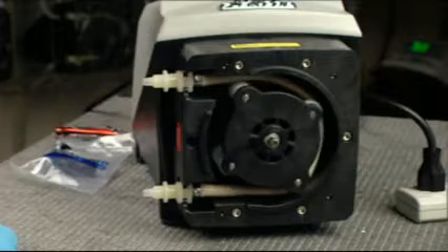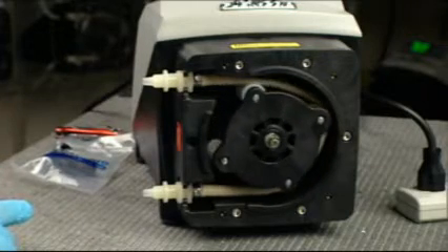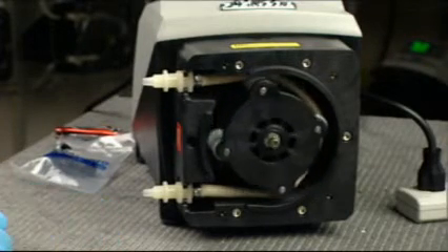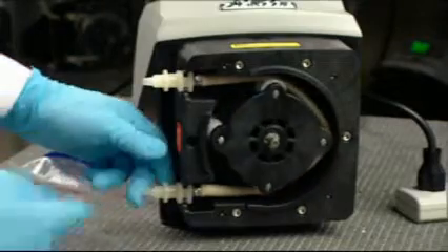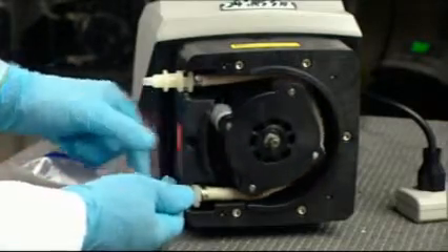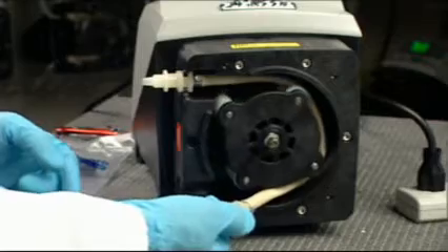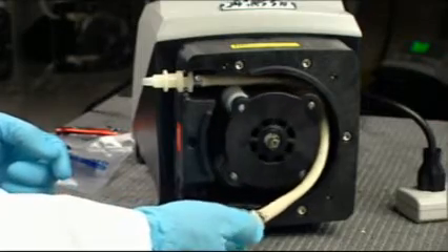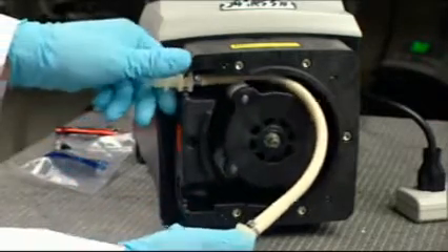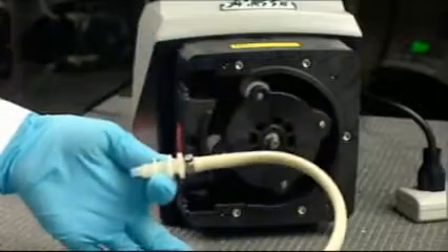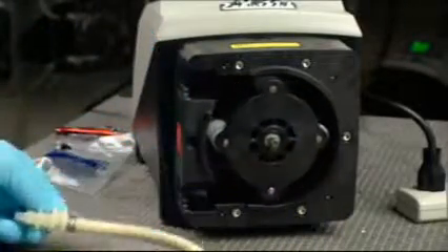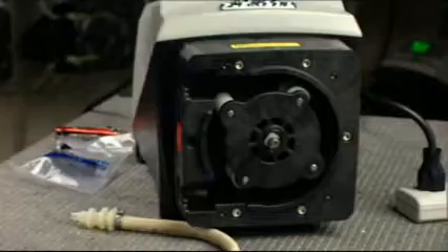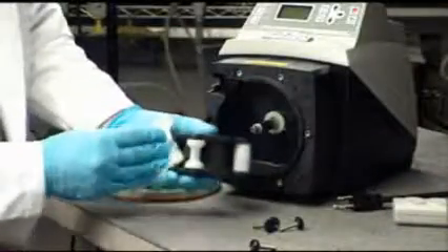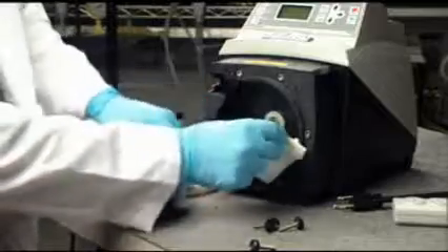Press the start button. Notice that the roller will only rotate at a slow, safe speed. Grasp the inlet pump tube fitting and pull the fitting straight out of the pump head. Allow the pump tube to automatically walk its way out of the pump head. Grasp the outlet pump tube fitting and pull the fitting straight out of the pump head. Press the stop button.